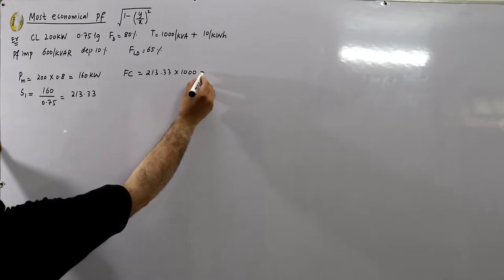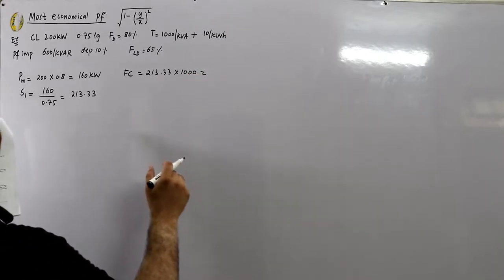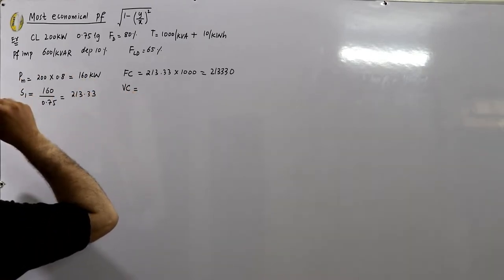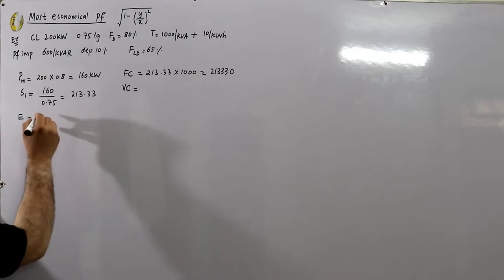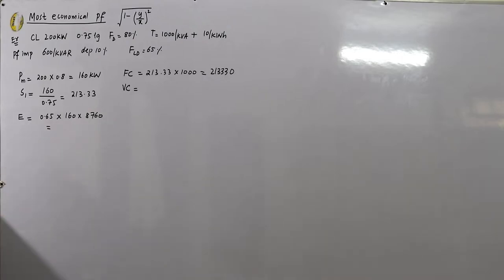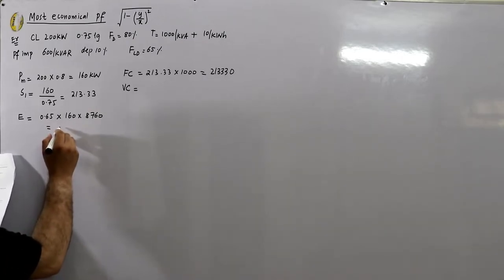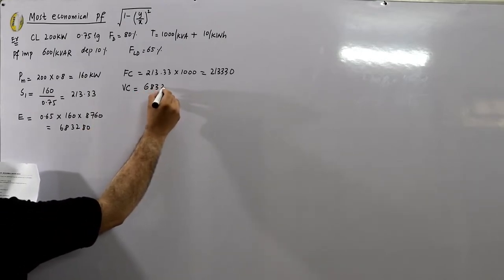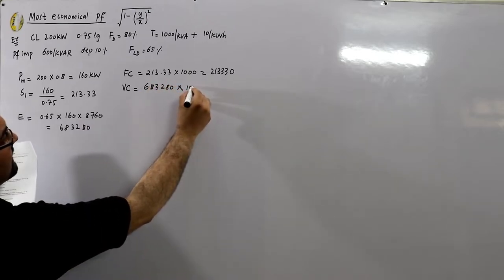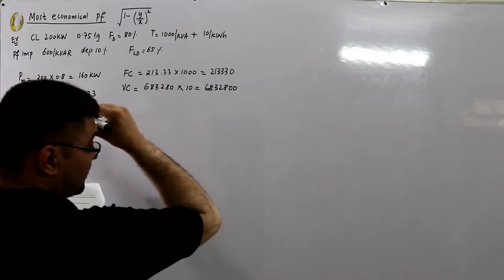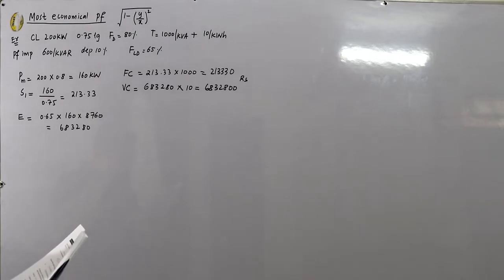The fixed cost is 213.33 multiplied by 1,000, giving 213,330 rupees. The variable cost is based on energy units. Energy units = load factor × maximum demand in kilowatts × time (8,760 hours annually), which comes out to 683,280 kWh. Multiplying by rupees 10 gives 6,832,800 rupees.